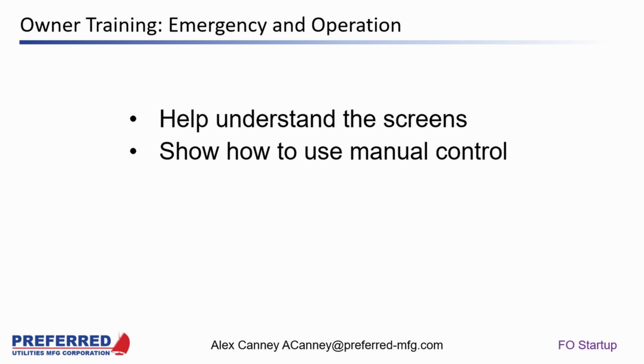Primarily, if you get an alarm, 9 times out of 10 it's going to be transmitted to a BMS system, so they'll get a visual of what that alarm is right away. But if not, and they're in the field, they go to the panel and look at the alarm ribbon at the bottom of all our screens to see what the current alarm or alarms are. Then they can make their determination on what needs to be done. So it's important with training to have them understand how to navigate the screen and know what they're looking at when they go to certain screens.